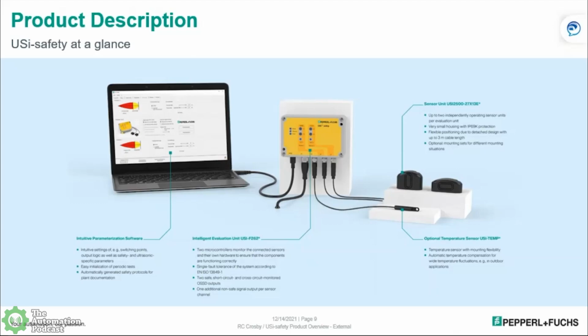From there, we go to the transducers. As I showed you earlier, they're very small, very compact. They come in 1.5 meter or 3 meter lengths of cable, so to get you out to your protected zone, away from the evaluation unit. And we also sell mounting brackets, should that be something that makes your life easier. There's also available a temperature sensor. Although it is not safe, it is necessary if you have this going into areas that may have fluctuations of 20 degrees or greater. And that just helps the sound cone compensate for those swings in temperatures.